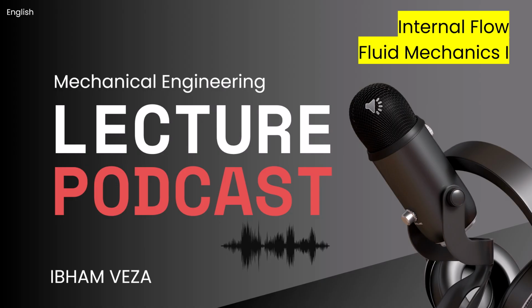The Venturi meter is generally considered the most accurate and causes the least permanent head loss because its gradual expansion section helps prevent flow separation. It's streamlined. Its discharge coefficient, CD, is very high, like 0.95 to 0.99. Then you have positive displacement flow meters. Think about the meter at a gasoline pump.